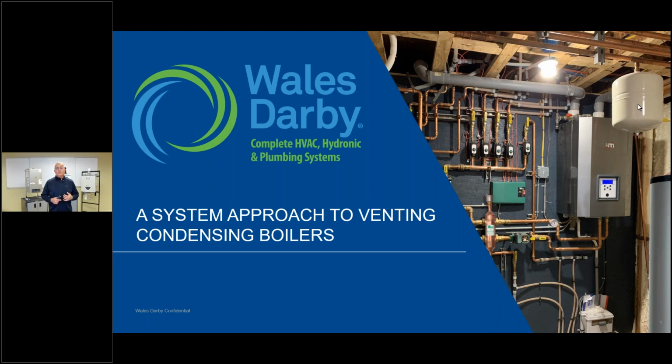Very, very important. So whether you're doing a condensing boiler, a condensing tankless water heater, a condensing tank type water heater, if I cannot vent it properly, if I have to really work hard to get the venting in there in some haphazard way, don't put that appliance in. Because the venting should not be a secondary system. The venting should be the priority because it's a life safety system. It truly is. All right, we have to keep that in the back of our mind, because since the last time I did this webinar, I've been out on many jobs and the venting has been a disaster.